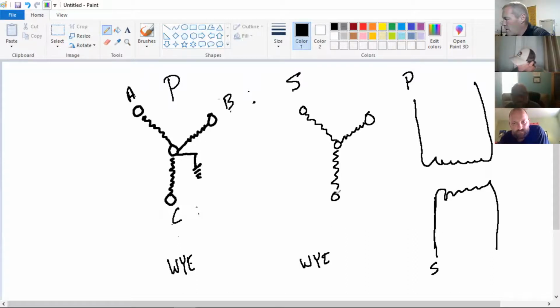We're just going to give different voltages. If my phase to ground voltage on my primary side is 7,200 volts, what is my line to line voltage? You've already answered that, somebody already answered that before. 12,470 volts, right?